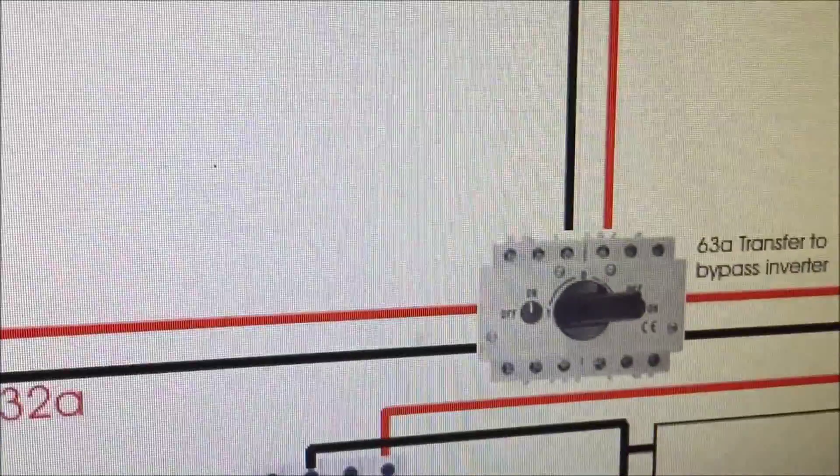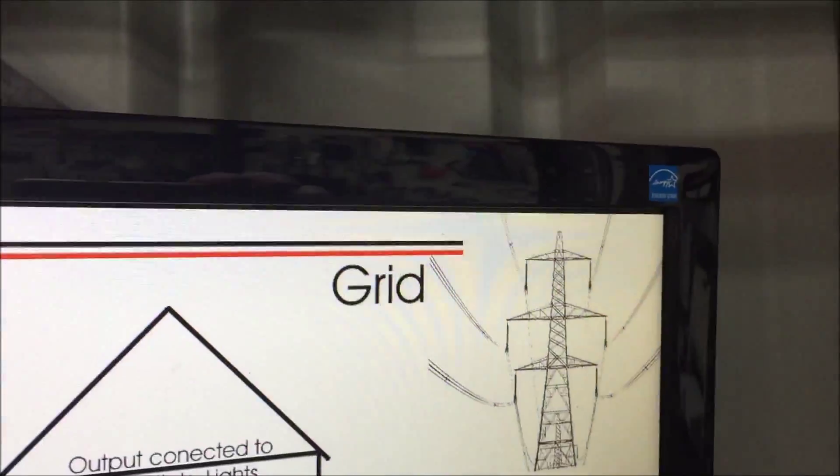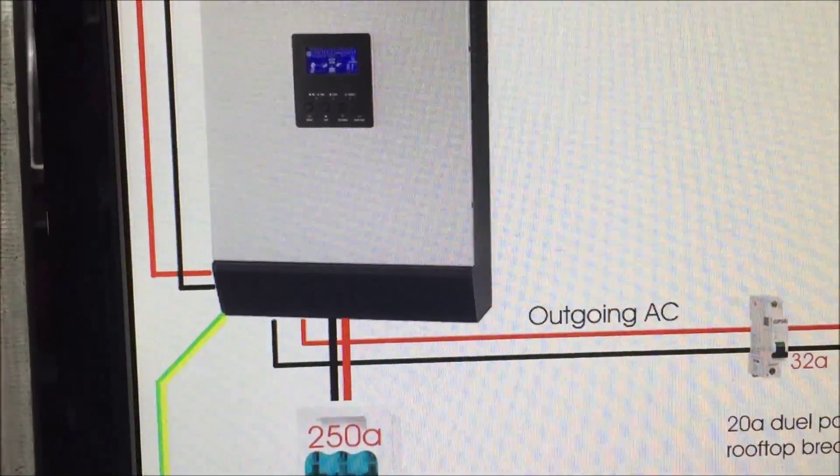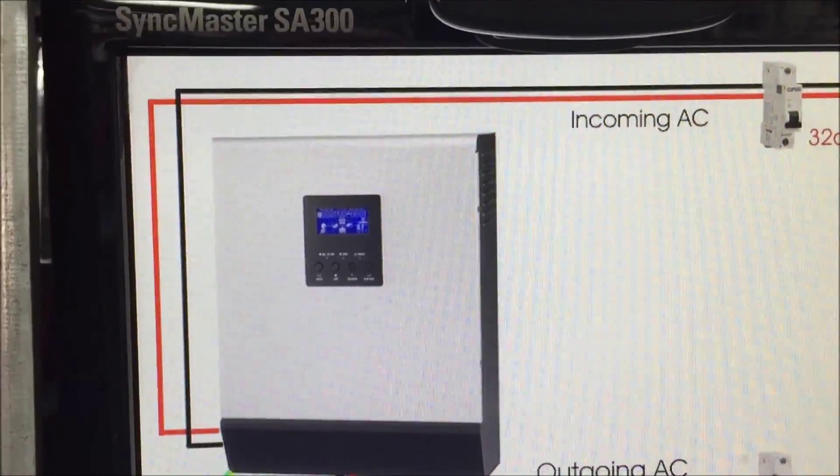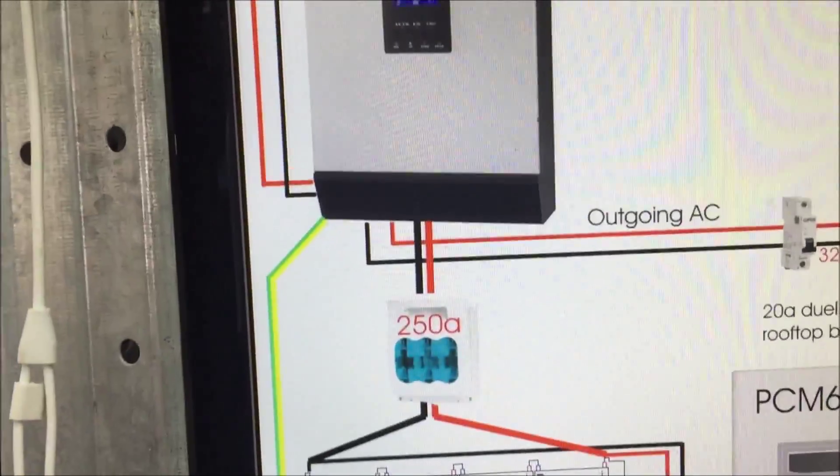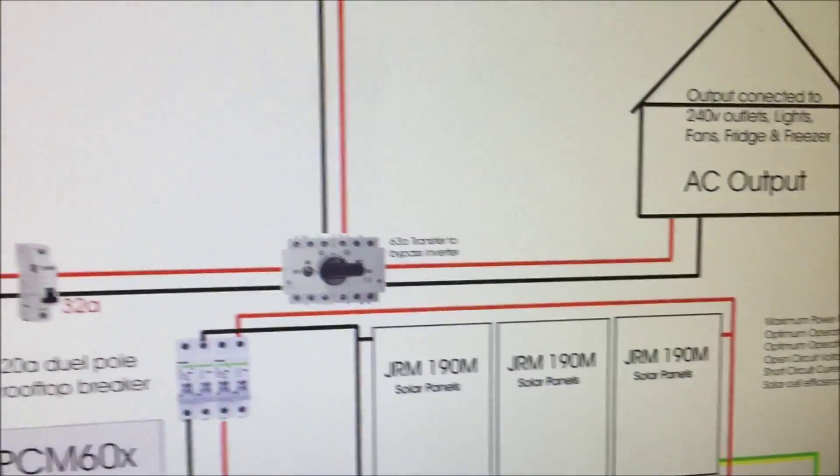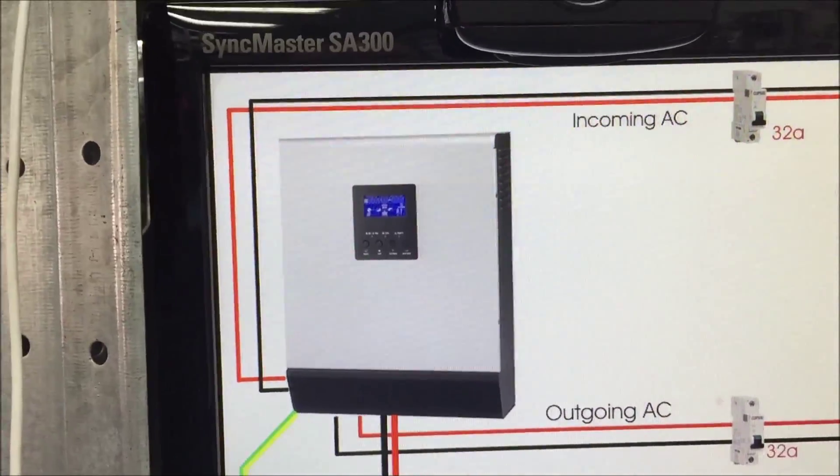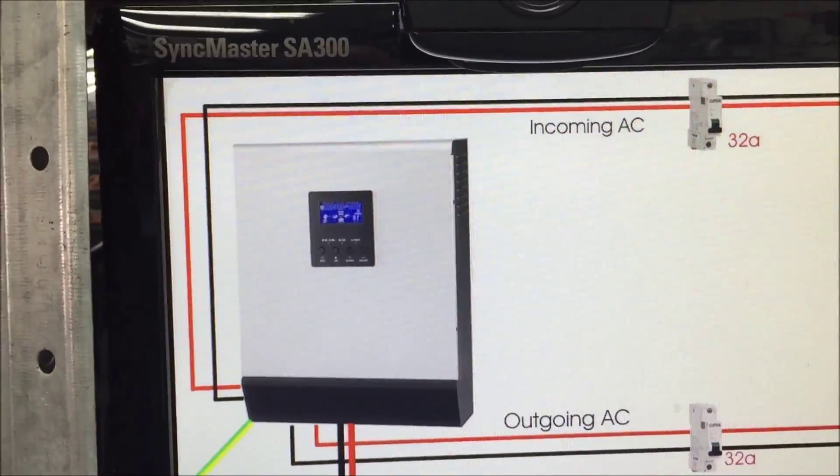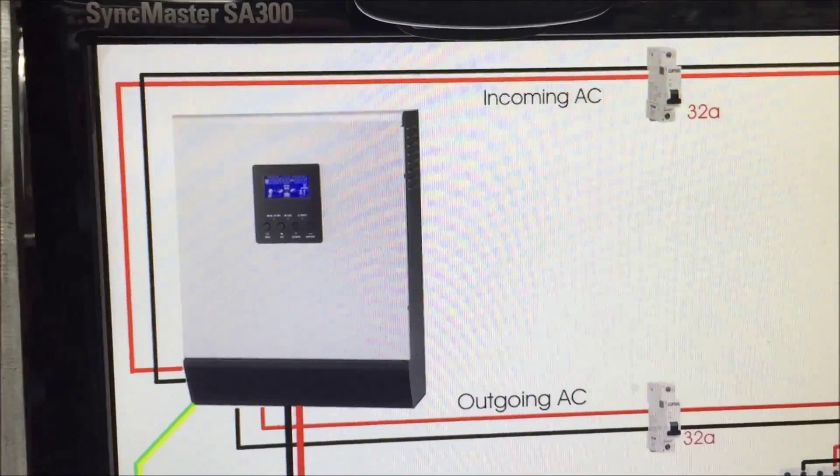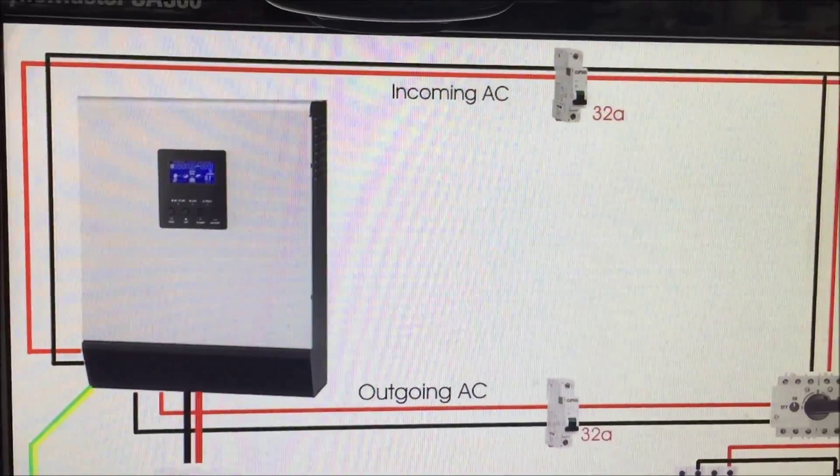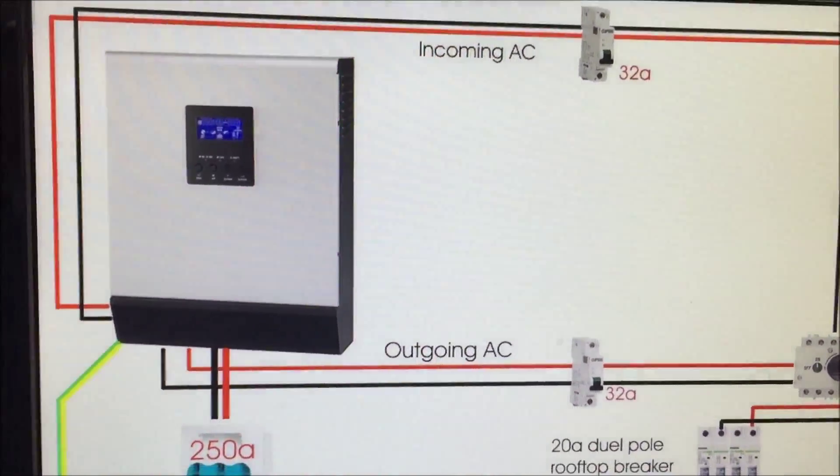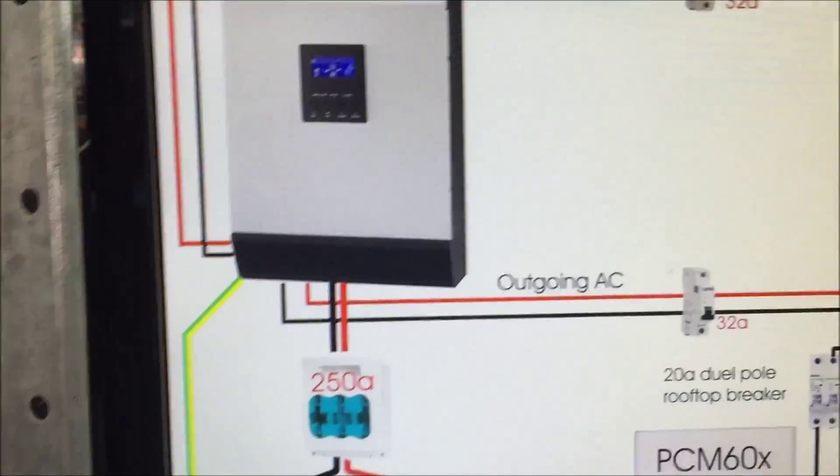So that's the important bit. You can't hook up the grid power to the outgoing power. You'll blow it up people. So it comes directly from the grid into your PIP and then PIP out into your house. This is not a grid tied unit so you can't put power back onto the grid because this thing will just launch and smoke and I've heard of a few people already doing that or more electricians doing it. So don't do it people.